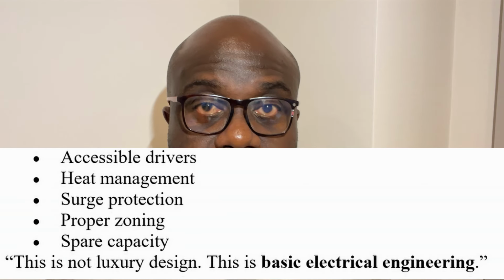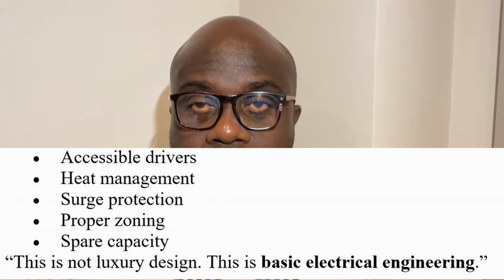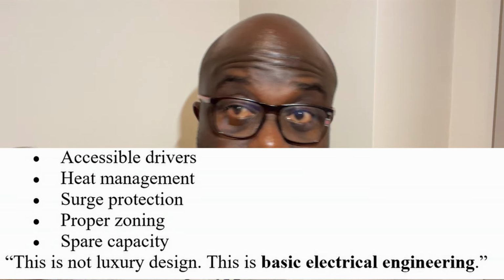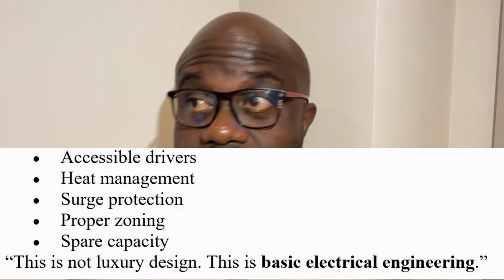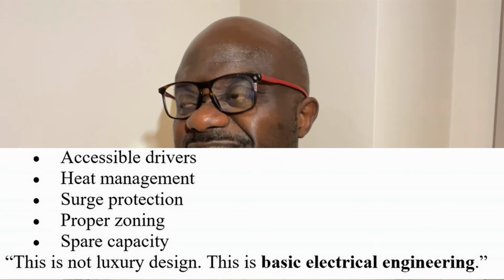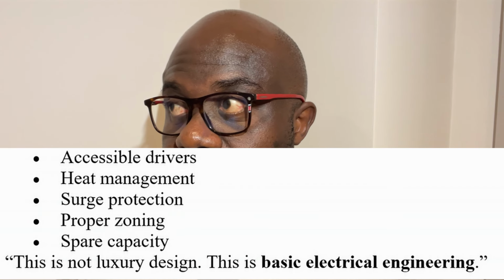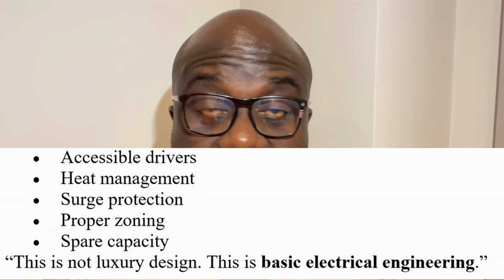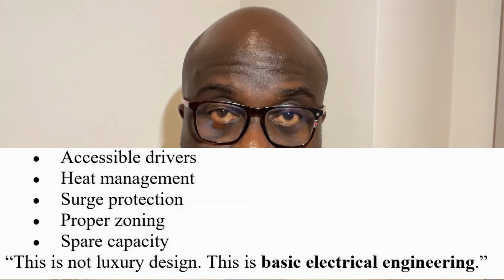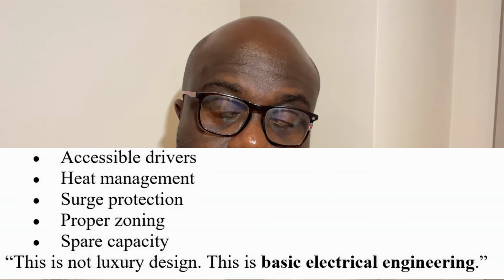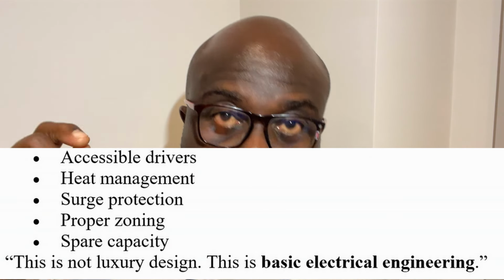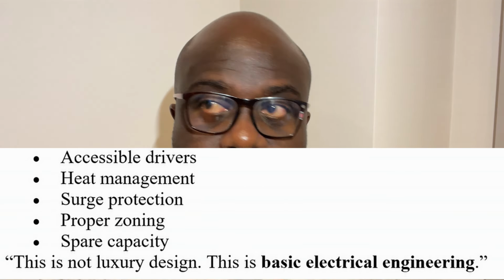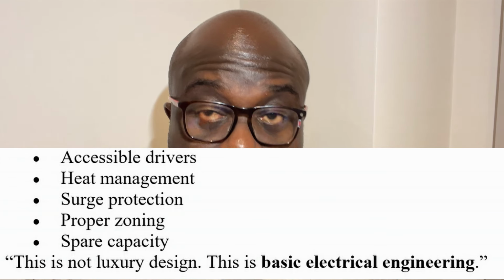What is the correct engineering approach? Number 1, the LED drivers must be fully accessible. Check that when you're buying your light fittings. Number 2, heat management. Make sure there's enough space between the POP or plasterboard ceiling and the concrete above. I would say 150 millimeters or 200 millimeters. In fact, 200 millimeters between the plasterboard and the concrete slab as a minimum, to ensure you have enough natural airflow around the drivers to dissipate the heat.